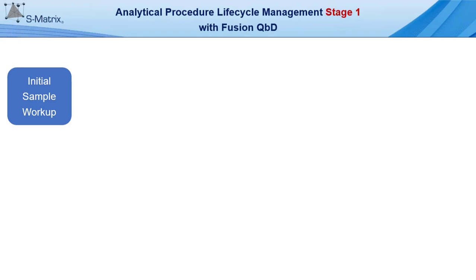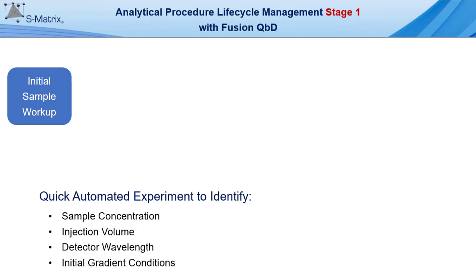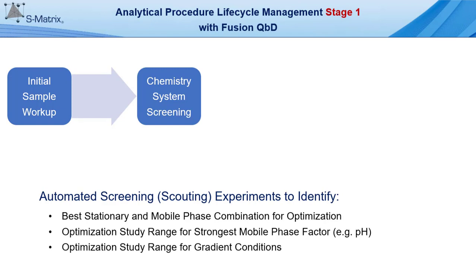Fusion QBD supports all phases of stage one, from initial sample workup to quickly identify the right sample concentration, injection volume, detector wavelength, and initial gradient conditions for method development. The initial sample workup leads into chemistry system screening, which with Fusion QBD automation enables rapid identification of the best stationary and mobile phase combination for optimization, the optimization study range for the strongest mobile phase factor or factors — for example, pH in a reverse phase method — and the optimization study range for the gradient conditions.